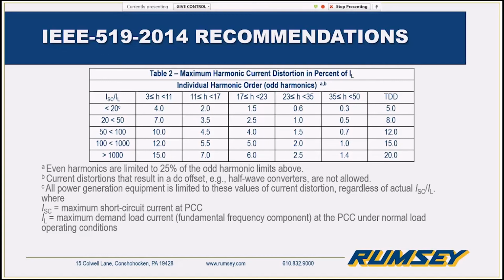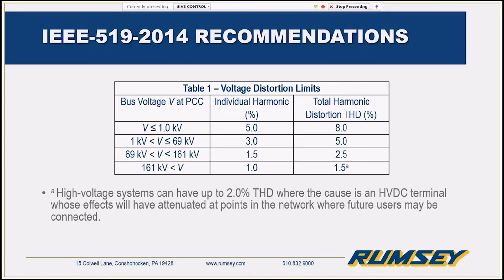And active filters in general and passive filters are designed to stop that current distortion, because current distortion causes the voltage distortion. When we're meeting that 5% specification, then we're also going to be meeting this voltage distortion limit as well.